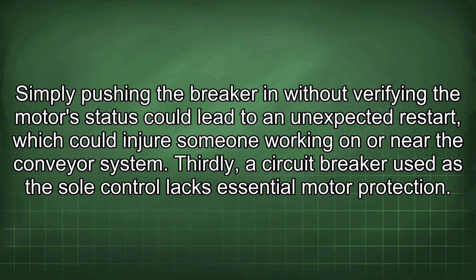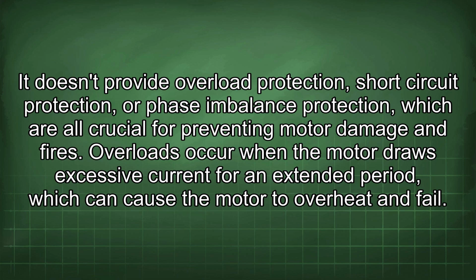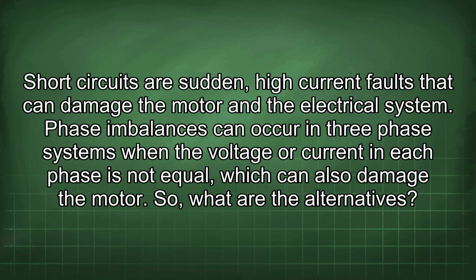Thirdly, a circuit breaker used as the sole control lacks essential motor protection. It doesn't provide overload protection, short circuit protection, or phase imbalance protection, which are all crucial for preventing motor damage and fires. Overloads occur when the motor draws excessive current for an extended period, which can cause the motor to overheat and fail. Short circuits are sudden, high current faults that can damage the motor and the electrical system. Phase imbalances can occur in three-phase systems when the voltage or current in each phase is not equal, which can also damage the motor. So, what are the alternatives?